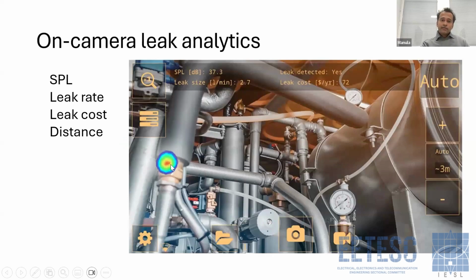These cameras not only detect and localize the leak source, but can also estimate the leak size based on the sound pressure level, or decibel level. They usually have inbuilt analytics for leak size estimation, and the user can give input parameters like cost parameters, so it can give the annual cost of the leak as well. It can also automatically detect the distance to the leak; in this case it detects 3 meters, thanks to the beamforming algorithm. These are the useful outputs of ultrasound cameras for leak source detection in industrial environments.